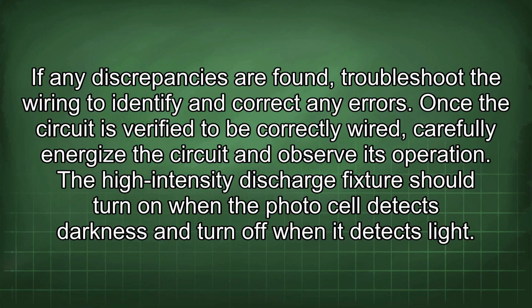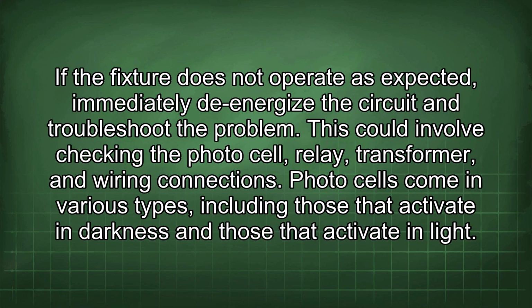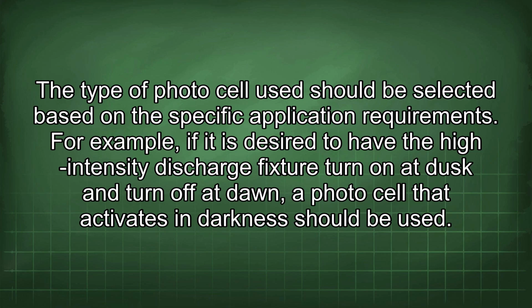The high-intensity discharge fixture should turn on when the photocell detects darkness and turn off when it detects light. If the fixture does not operate as expected, immediately de-energize the circuit and troubleshoot the problem. This could involve checking the photocell, relay, transformer, and wiring connections. Photocells come in various types, including those that activate in darkness and those that activate in light. The type of photocell used should be selected based on the specific application requirements.